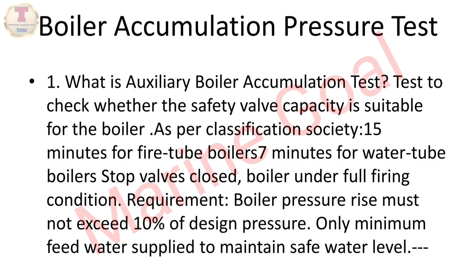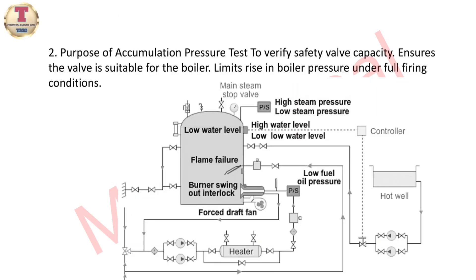Test conditions: stop valves closed, boiler under full firing condition. Requirement: boiler pressure rise must not exceed 10 percent of design pressure. Only minimum feed water is supplied to maintain a safe water level.